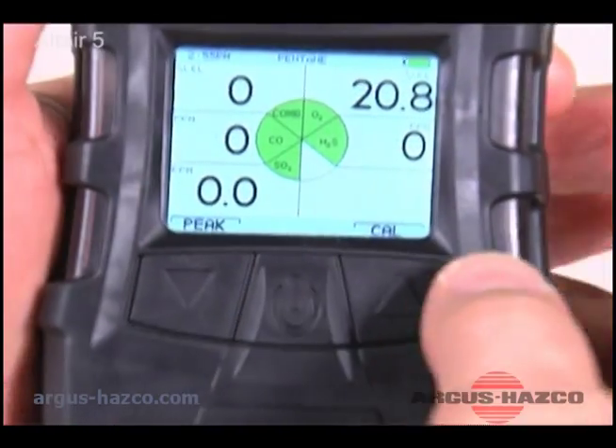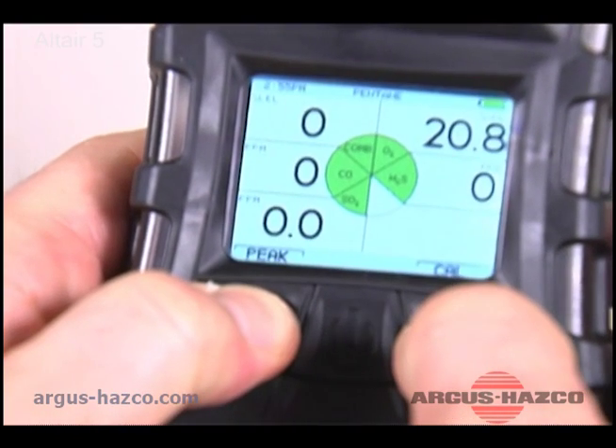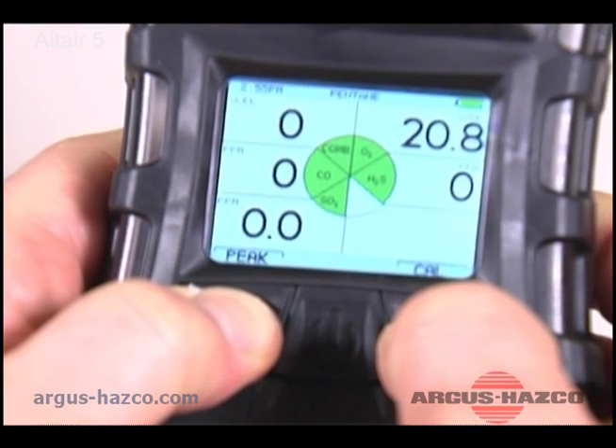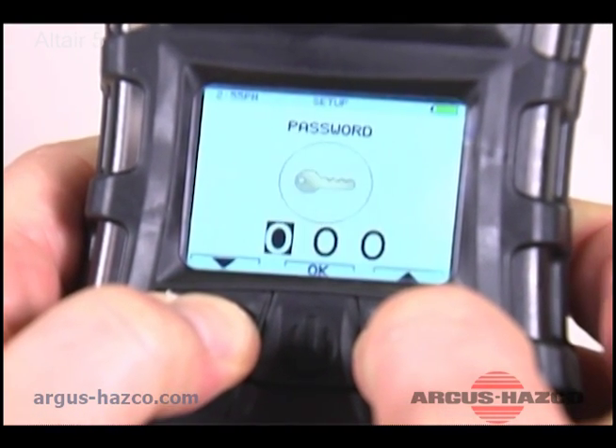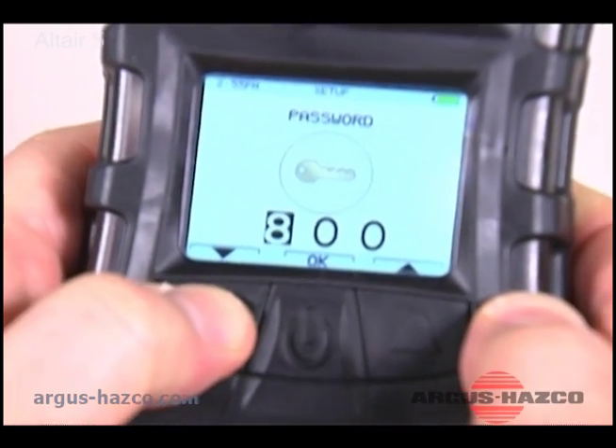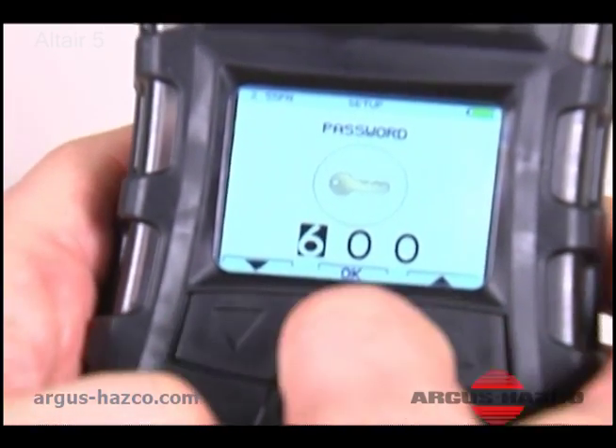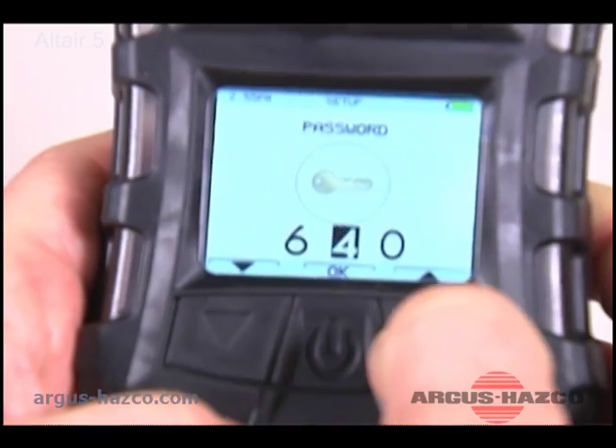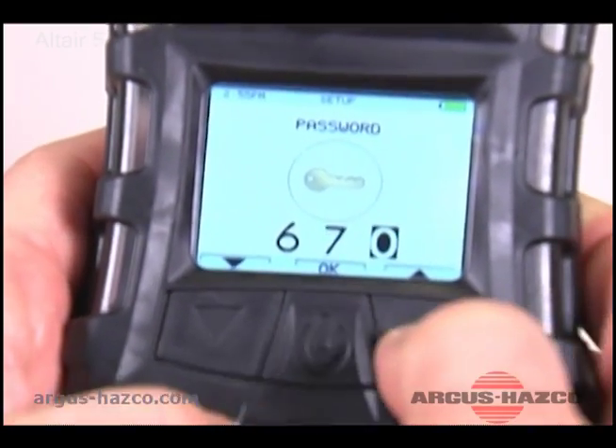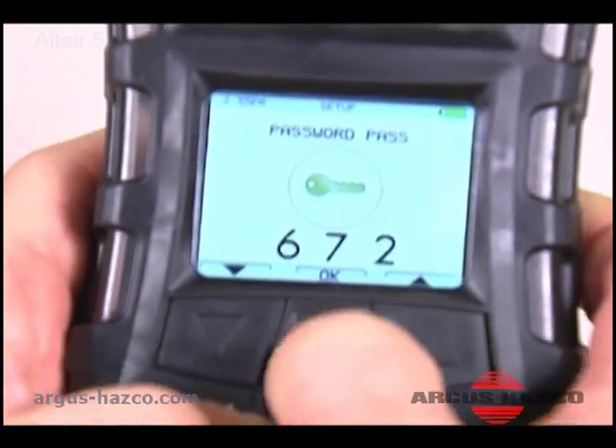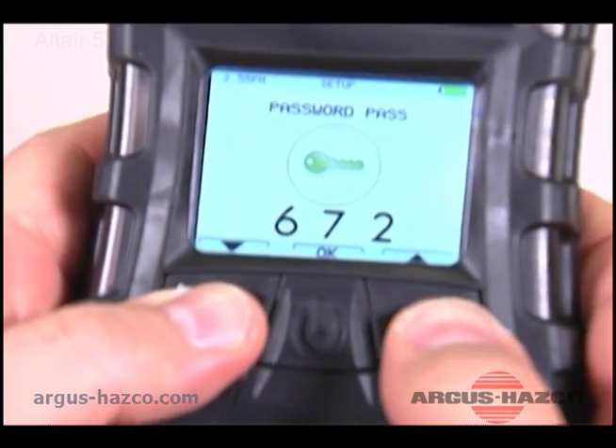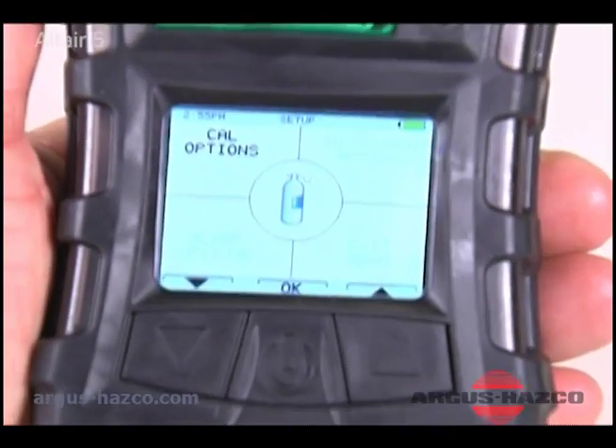If necessary, adjust the values on the calibration setup page. From the main page, press and hold the up and down arrow buttons. Use the up and down arrows to enter the password. The default password is 672. Use the calibration options menu to change calibration cylinder values.